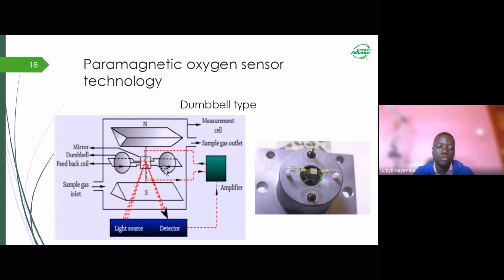So when a stream of a gas mixture that is to be analyzed flows around this assembly, it fills the sensor cells, and because of the paramagnetic property of oxygen, its molecules tend to accumulate between the poles of the magnet. So as the oxygen is being attracted to the magnetic field, it displaces the glass spheres, causing the suspension rotation together with the mirror.